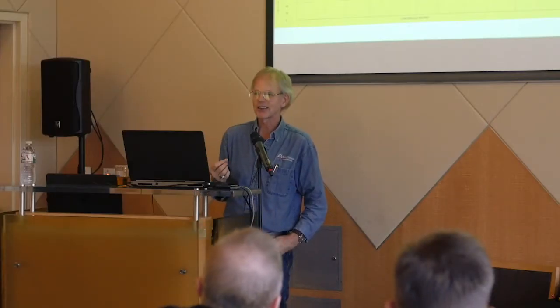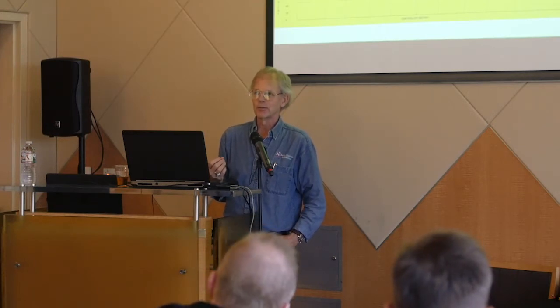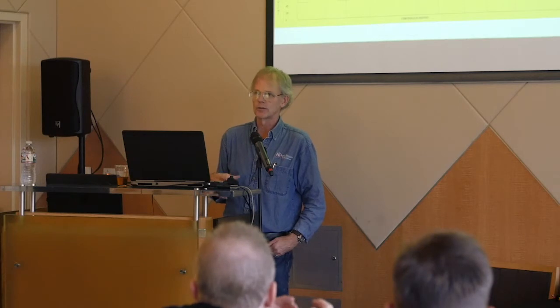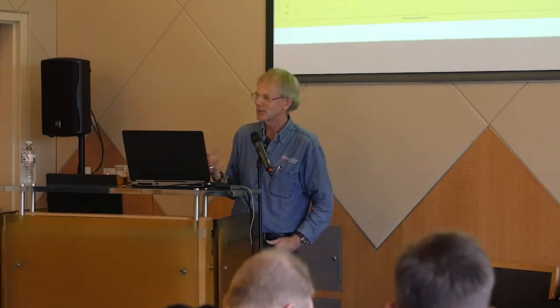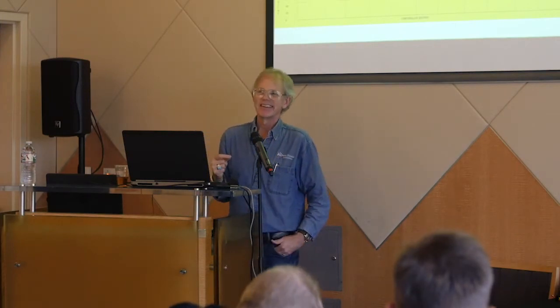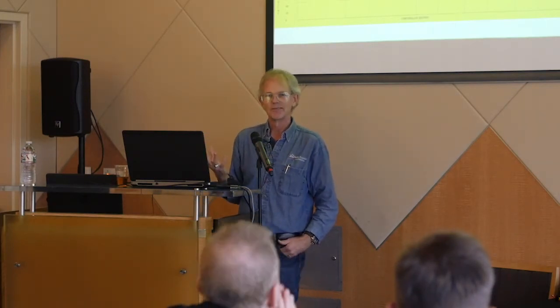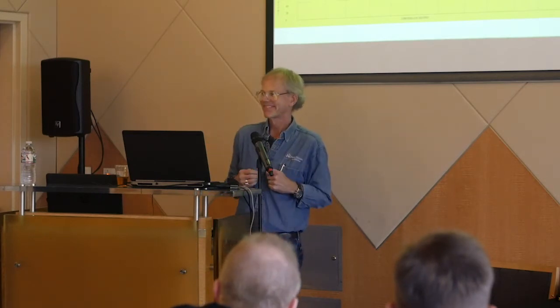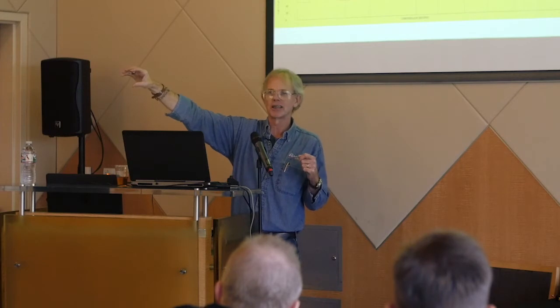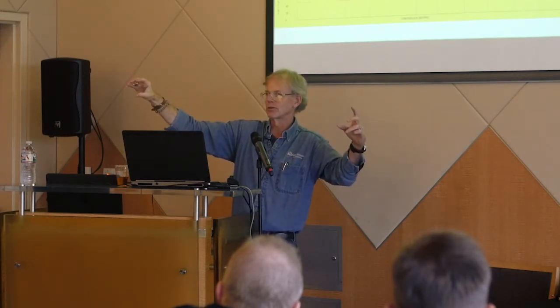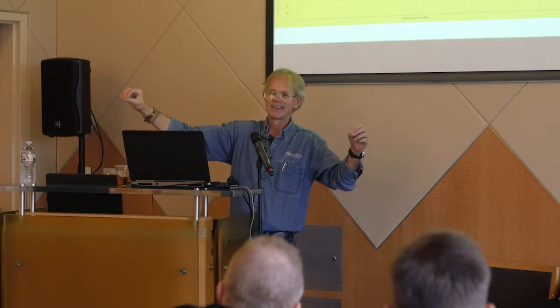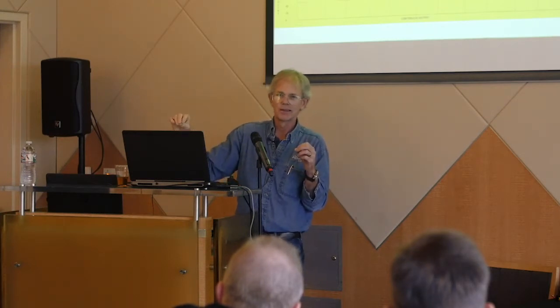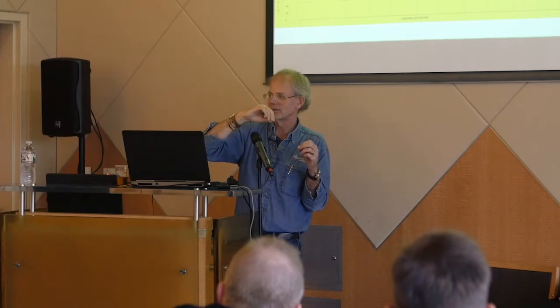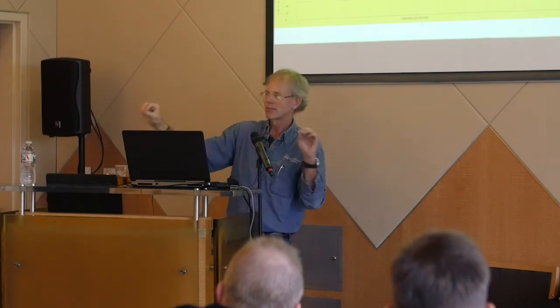So I called him back a couple days later and I said, so how'd that work? And he said, the Partlow one was great. The Fuji one wasn't so great. And Tom was very colorful, so he actually said it more colorfully than that. But basically the message was, he didn't like the Fuji one. And I was down there the next day and we couldn't figure out why that would be. So we decided, let's swap them. In other words, he had put the Fuji one in one air handler and the Partlow one in a different one, controlling the inlet vanes, I think. And when we swapped them, they both auto-tuned. So there was something about the dynamics of the one system that the Fuji controller could deal with, but it couldn't deal with in the other system, but the Partlow could deal with both of them.